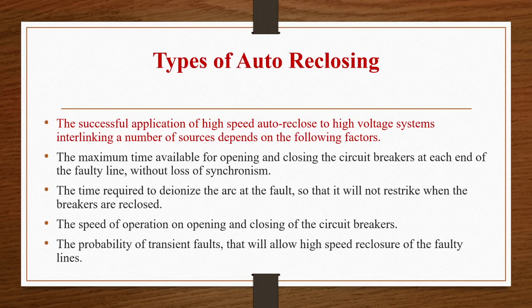Now let us see the successful application of high-speed auto reclose to high-voltage systems interlinking a number of sources will depend on the following factors. What are the factors we are going to see now? The maximum time available for opening and closing the circuit breakers at each end of the faulty line without loss of synchronism. So what is the first factor? Maximum time available for opening and closing the circuit breaker at each end of the faulty line, and that too without loss of synchronism.